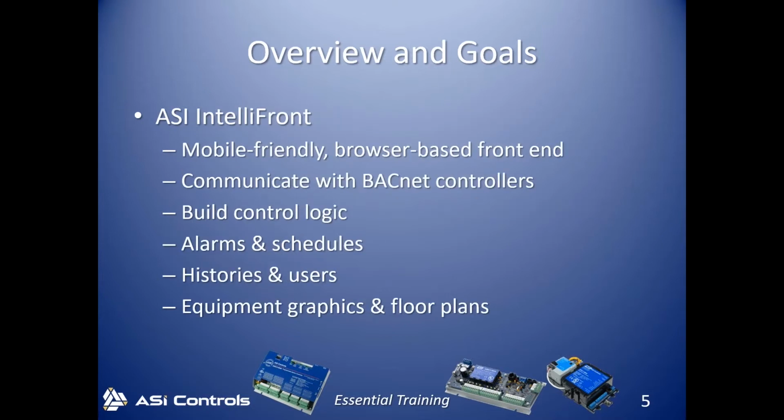Those of you that are staying on for IntelliFront next week, that's one of our newer front-end options designed for mobile, which is different than our older WebLink software, which worked mainly with Internet Explorer. IntelliFront will use the BACnet protocol to communicate with the controllers, but it does also contain what are actually referred to as connectors, ASI protocol connectors, so you could upgrade an older WebLink project perhaps to have a new mobile-friendly front end.